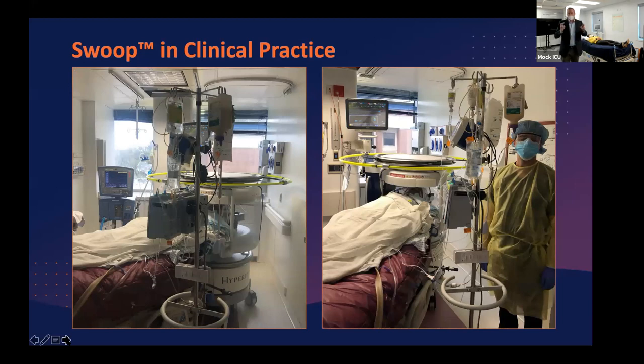Zooming in on an MR suite: a COVID-positive, intubated patient, next to the drips, vents, HVAC equipment, patient monitor — this is the environment. The young resident here generated the scans. We train people in about 30 minutes how to use our system — 15 minutes teaching you how to drive your MR device down the hall and into the room, and the other half with an iPad choosing sequences: T1, T2, DWI — which one am I ordering and in what sequence? That consists of our training — about 30 minutes per user.